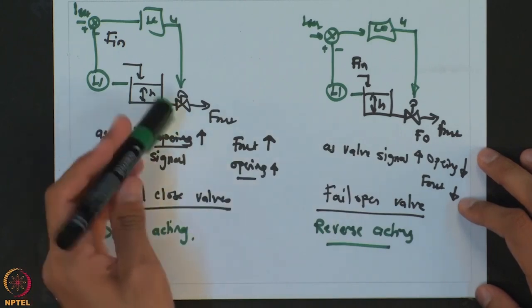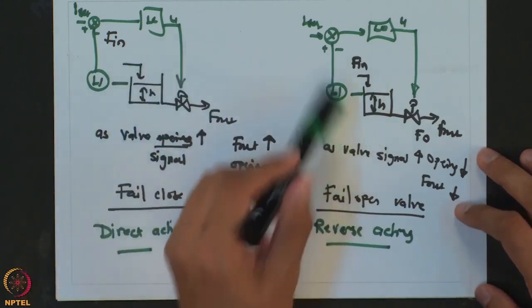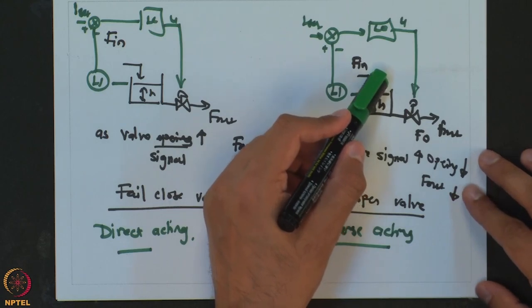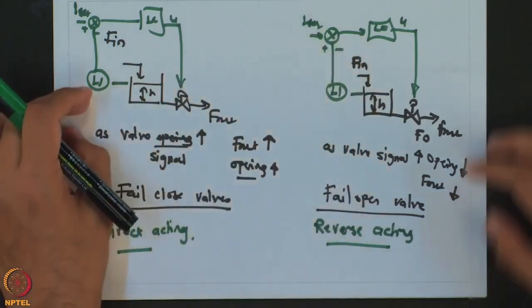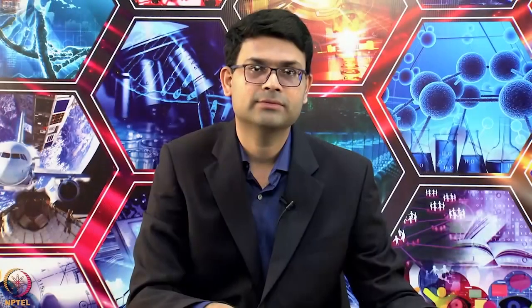If we mistakenly use a direct acting controller for a fail-open valve system, it will never be able to maintain the level, and we will see why through mathematical analysis as well. So it is very important to know the type of controller action. Let us now look at what are the different types of control actions possible in feedback control. The first and simplest control action — simplest in terms of implementation — is on-off control.